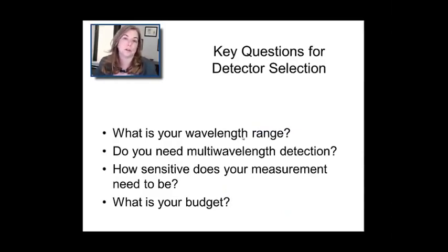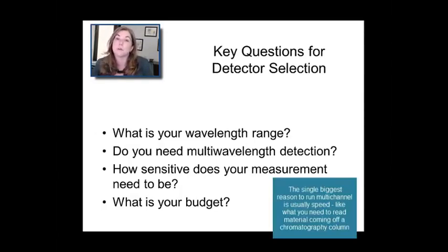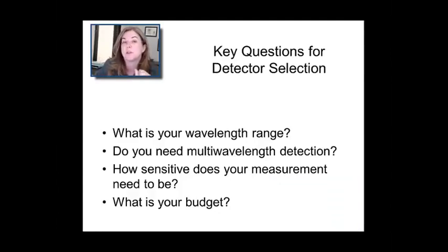When you're choosing a detector for a spectrophotometer, really the first and foremost question is, what is your wavelength range? We didn't really talk a lot about the infrared detectors because you can use CCDs for some of the near IR, but they're pretty simple systems. MCT or mercury cadmium telluride systems are the ones I'm familiar with. You often have to cool them with liquid nitrogen so they don't pick up a background. But other than that, they're pretty standard. And they're not what limit the performance of infrared spectrometers. If you need multi-wavelength detection in a detector, you're going to need to pick a CCD or a photodiode array for optical absorption. You need to think about how sensitive your measurement needs to be. And assuming you're not measuring black samples, at least for absorption spectroscopy, you're not going to be bumping up against not having enough photons. But in fluorescence spectroscopy, or Raman spectroscopy, that's a whole other issue. And we won't be going to those, but just be aware that typically you're going to have plenty of photons if you're doing optical or infrared absorption spectroscopy of the type we're talking about.